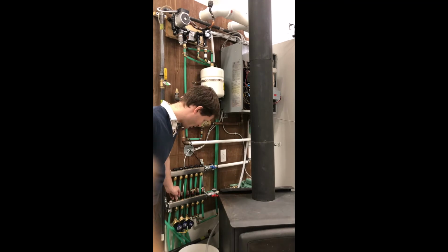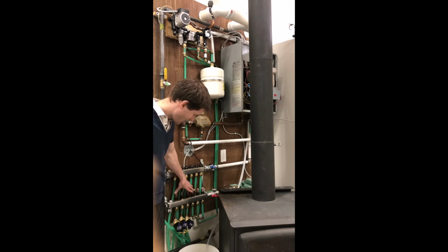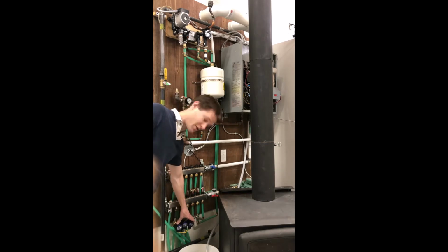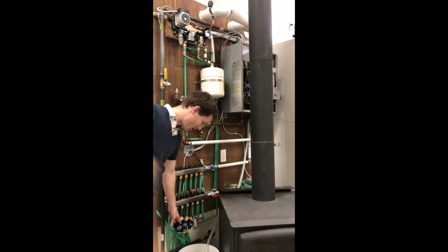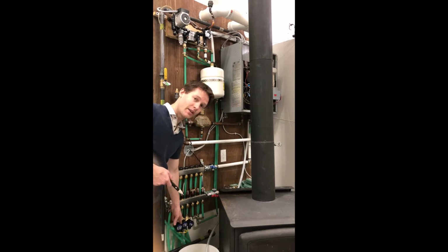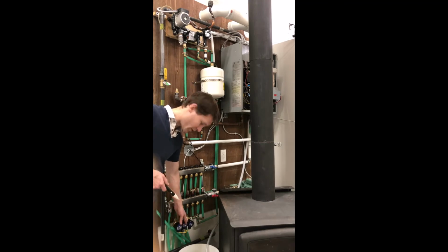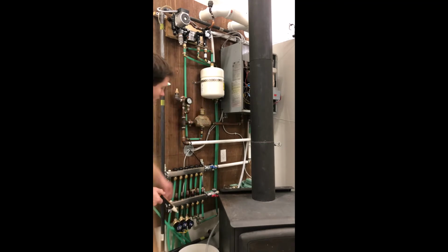Then you've got your little flow control valves, which tell you how much fluid you're passing through the system here. These 3 loops are for in-floor heat. We've got our isolation solenoids on these, and when we get a call for in-floor heat in the garage, these solenoids — normally closed — pop open, and everything else turns on, sending hot water down into the floor.